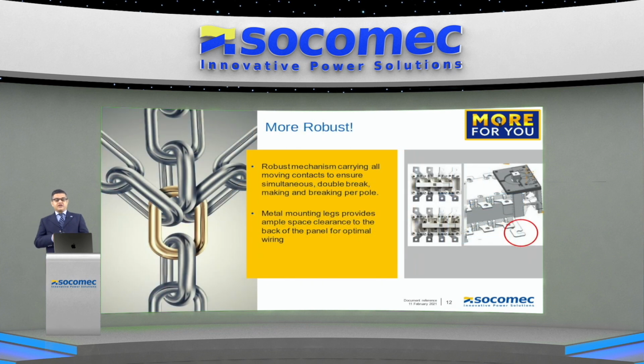Robust because the mechanism is built for carrying all the moving contacts to ensure simultaneous double break, making and breaking per pole, with metal mounting legs. We go down to all these finer details - metal mounting legs for a more secure mounting position, providing ample space clearance to the back of the panel for optimum wiring, contributing to enhanced ergonomics for the system integrator's wiring personnel.